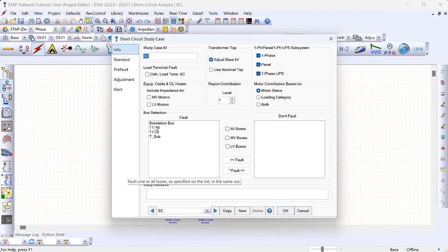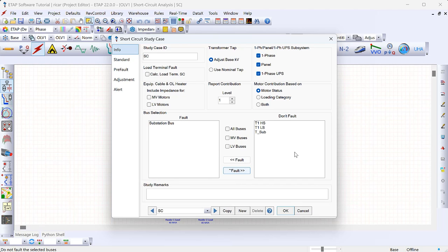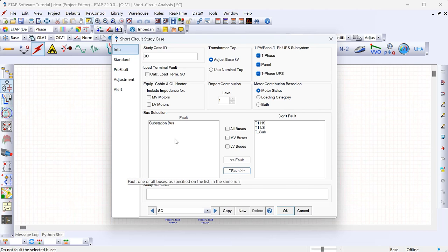For example, if I just want to fault the substation bus I can select the others and move them to the right — when I hit 'Run Short Circuit', ETAP will not fault those buses. That's sometimes beneficial if you have a very large model with many buses, because the short circuit study might take time. If you're only interested in some buses you can just include those, which helps speed up the fault current calculations.